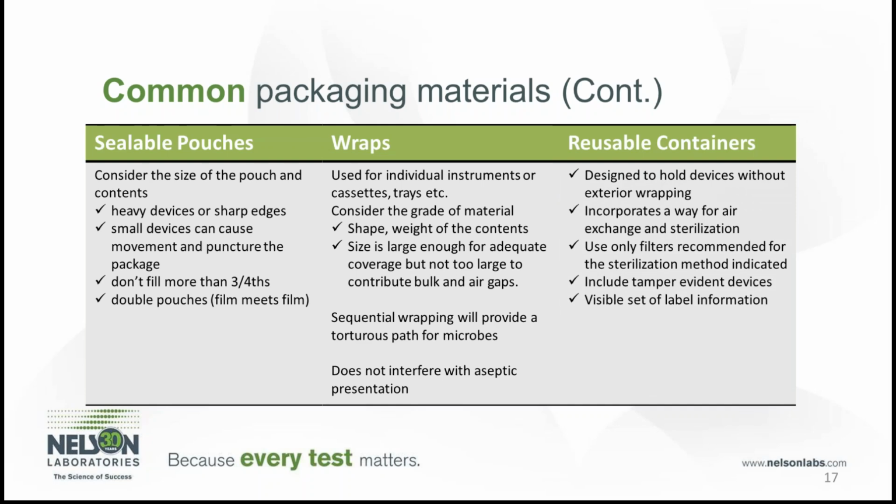Reusable containers are great because they are designed to hold not only a single device, but also device and some of the equipment or tools required for an operation or procedure. A lot of these reusable containers incorporate filters either in the lid or the base that can help aid in air exchange for sterilization for EO or steam. Keep in mind that if you do have filters in those, you do need to make sure that the filter material that you are using does still provide that adequate sterile barrier to the contents inside.